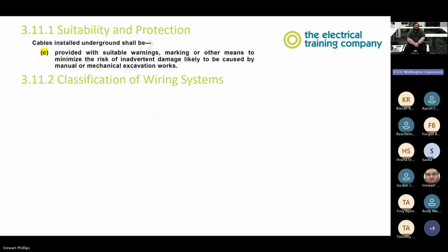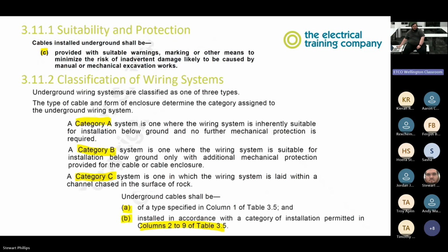Cool. Suitability and protection. So cables installed underground shall be provided with suitable warnings, markings, or other means, minimizing risk of inadvertent damage likely to be caused by manual or mechanical excavation work. So making sure we put the danger tape down. Cool. And we talked about the classification of wiring systems. So they're either A, B, or C. A is inherently suitable for installation below ground and no further mechanical protection. B, suitable for installation below ground with additional mechanical protection provided by the cable or enclosure. C is one in which the wiring system is laid within a channel chased in a rock surface. Underground cables shall be A, type specified in column 1 of table 3.5, installed in accordance with the category of installation permitted in columns 2 to 9 of table 3.5. So either they're a type specified in column 1 or installed to columns 2 to 9 of that table.